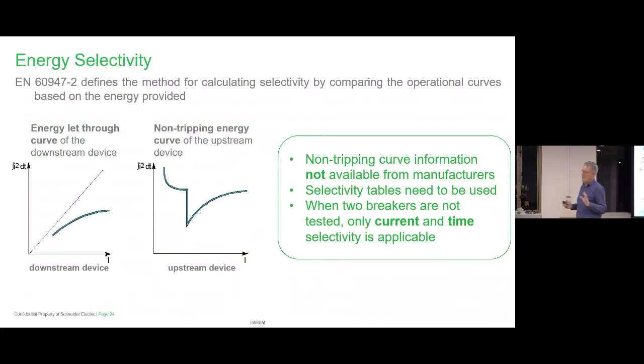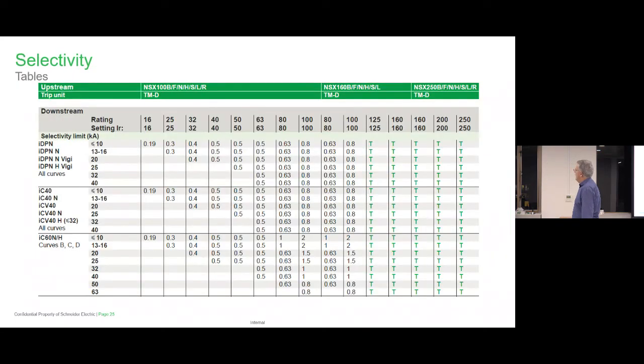Well, see, there's no test for that for this level of concern, which is energy selectivity. So in the energy ones, this is the downstream device in relation to the upstream device. The upstream one can't operate. It must be higher in terms of its energy capability than the downstream. And yes, we give details on that. And this really leads on to the table that you would see. We have pages and pages and pages of these things. So this is just a little example I'm looking at here.